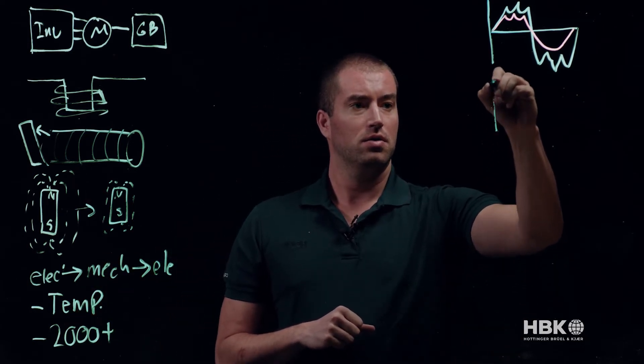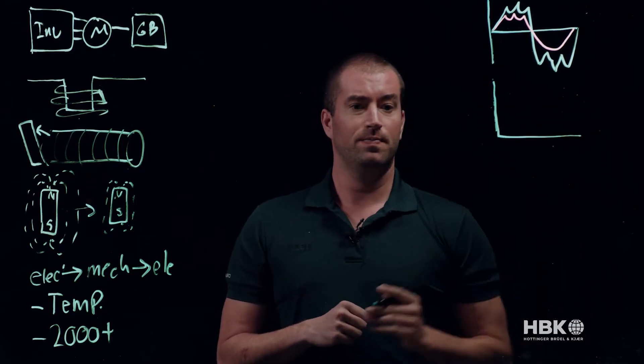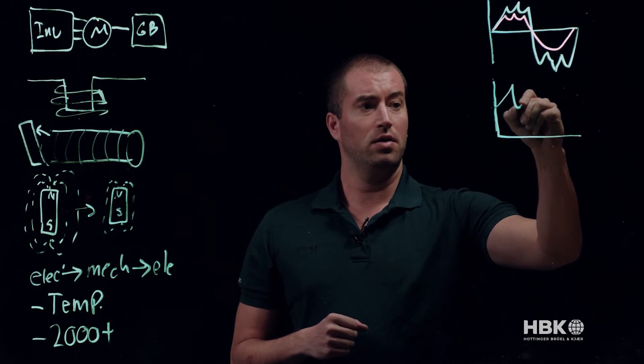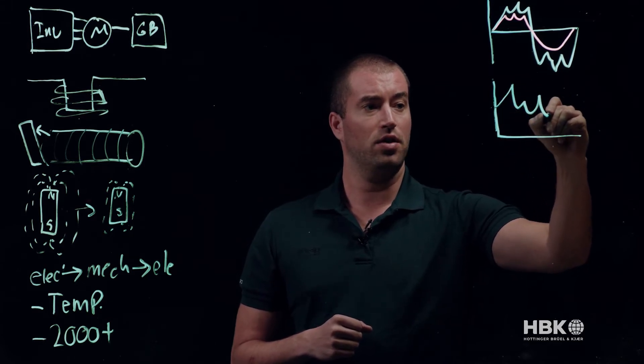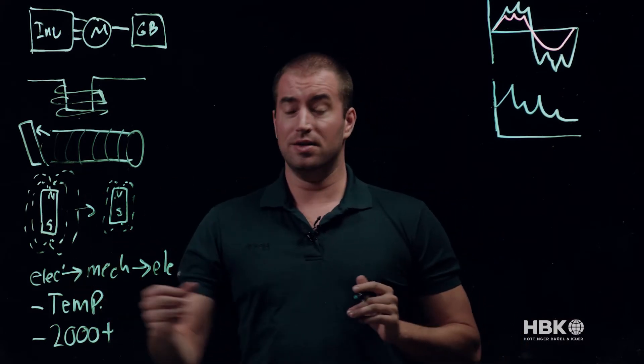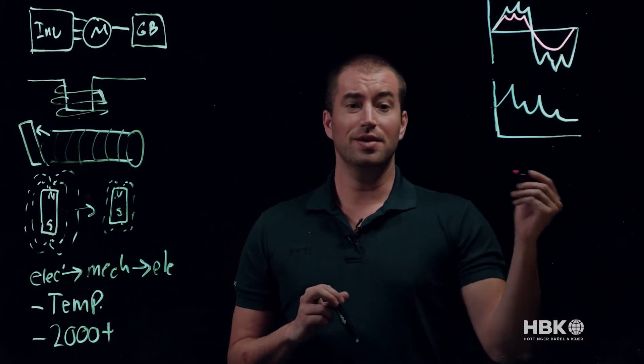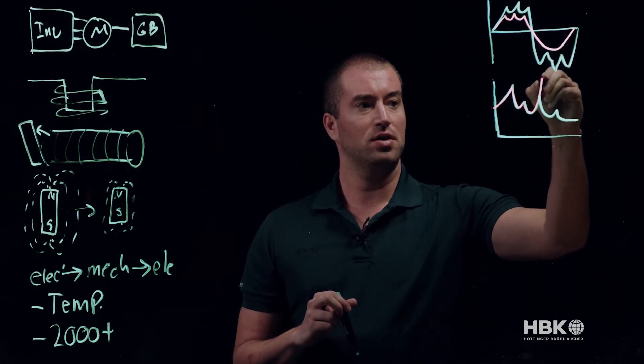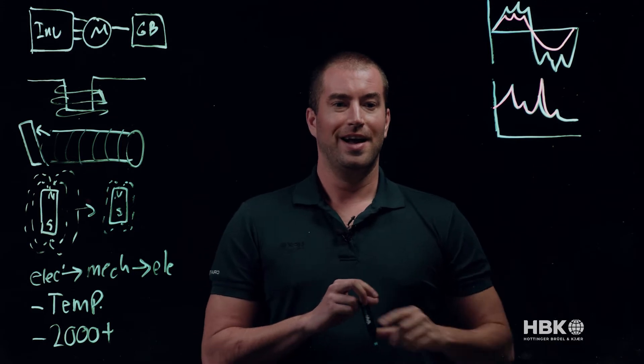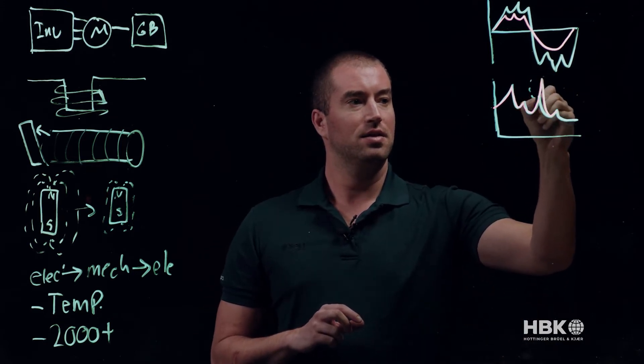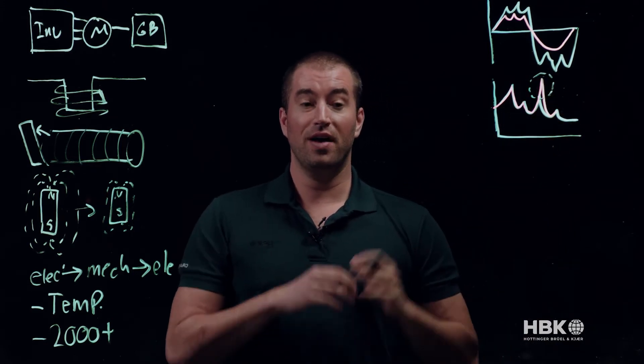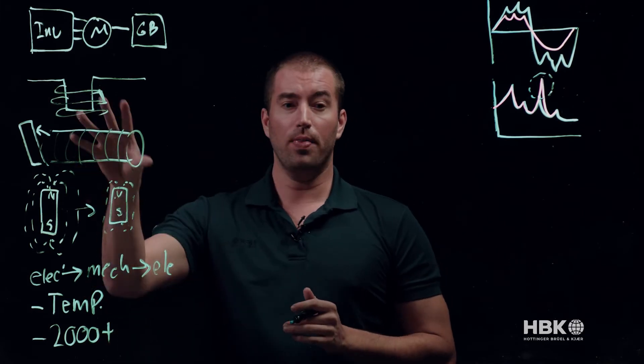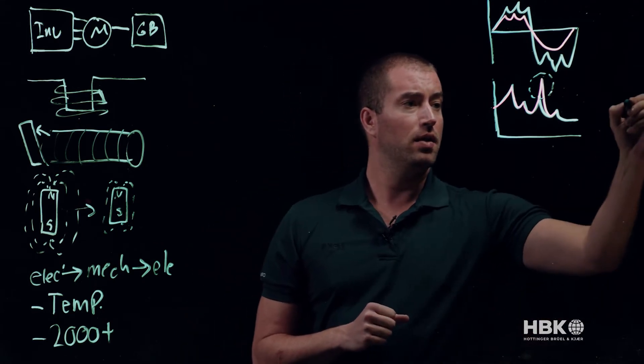We can also look at the harmonic output of the machine. We can look and see here's my fundamental, here's my third, here's my fifth. And over time, over that 2,000 hours, we can see if there's long-term changes. Maybe my fundamental stays the same, but my fifth starts to drastically increase. This can help us identify if something's going to fail and again try to accelerate that testing or identify what the mode of failure is.